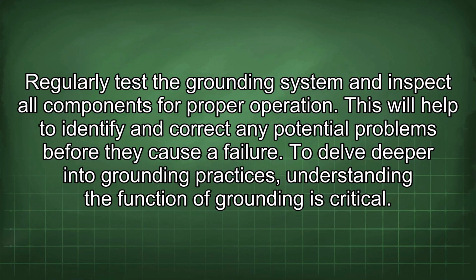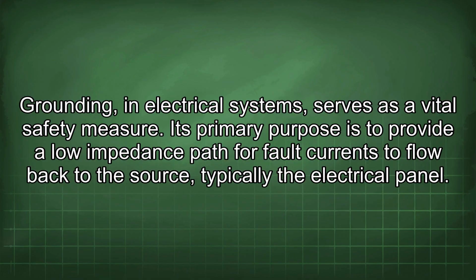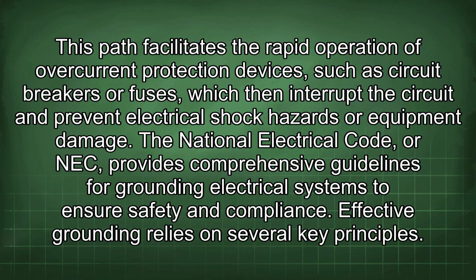To delve deeper into grounding practices, understanding the function of grounding is critical. Grounding, in electrical systems, serves as a vital safety measure. Its primary purpose is to provide a low impedance path for fault currents to flow back to the source, typically the electrical panel. This path facilitates the rapid operation of overcurrent protection devices, such as circuit breakers or fuses, which then interrupt the circuit and prevent electrical shock hazards or equipment damage. The National Electrical Code, or NEC, provides comprehensive guidelines for grounding electrical systems to ensure safety and compliance.